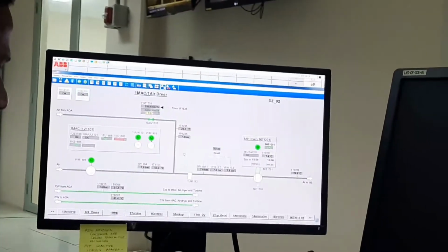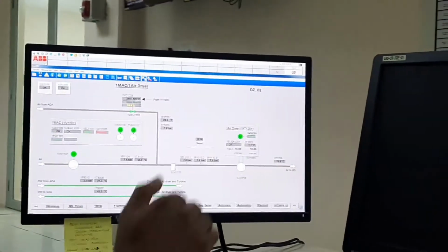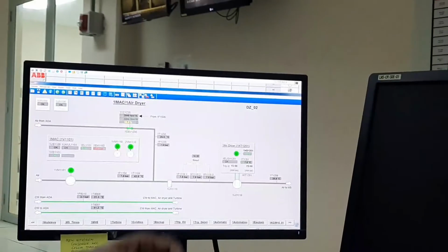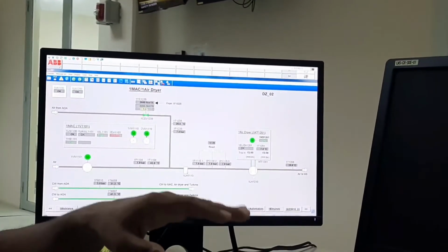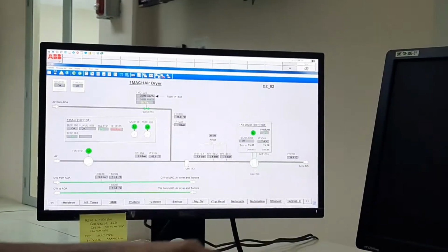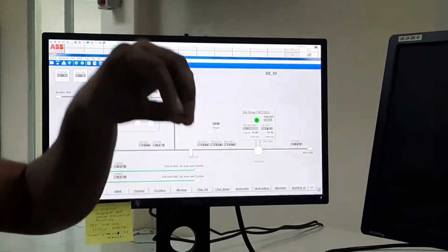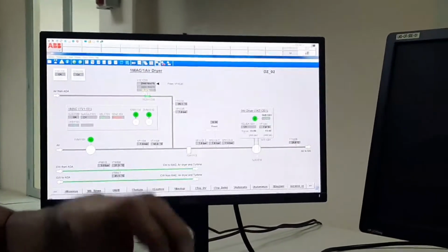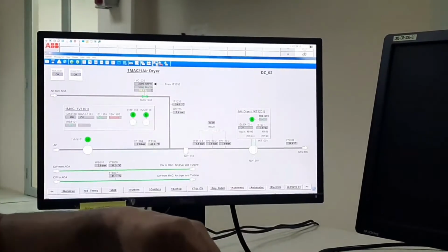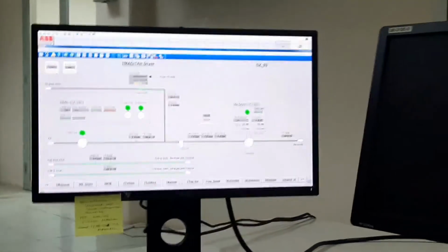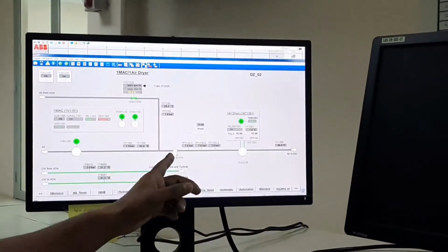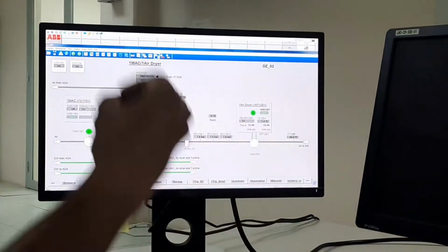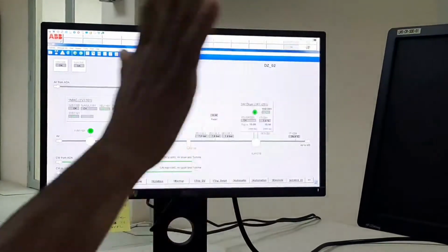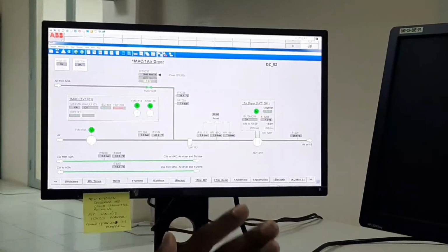So 3,000 normal meter cube air, 7.6 kg pressure, 28 degree temperature, will go through the air filter. When it passes through the air filter, some moisture is removed. On this air filter you have seen locally there is an auto solenoid valve. When air is passing, some condensate accumulates on the filter side, so this solenoid valve automatically removes the condensate. The main function of this air filter is removing condensate, because we need dry air. Moist air is not good for the plant.